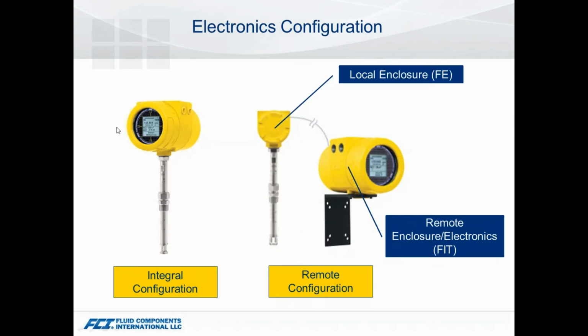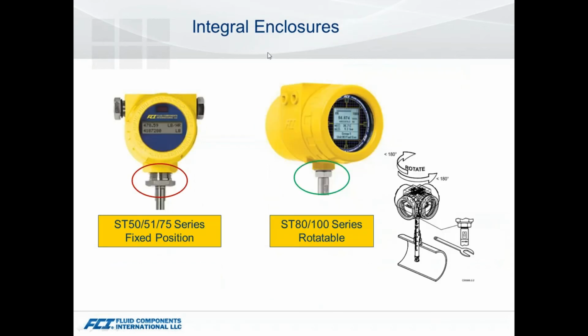A lot of basic things that you see: integral versus remote configurations, integral enclosures, things to look at on the Economical series. That flow element is threaded into the enclosure and there's no adjustability to it. Whereas on the newer, higher end units, we have a locking nut where you can rotate that enclosure 180 degrees depending upon where it needs to be oriented. So that one's very flexible with regards to selecting a flow direction and orientation.